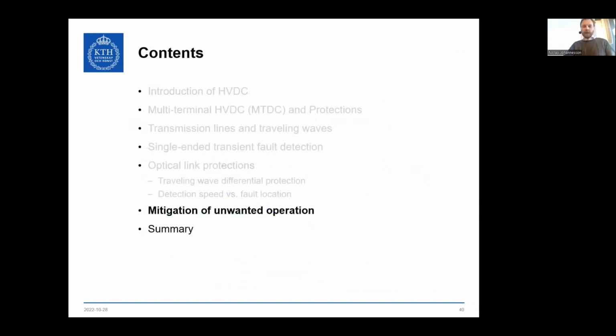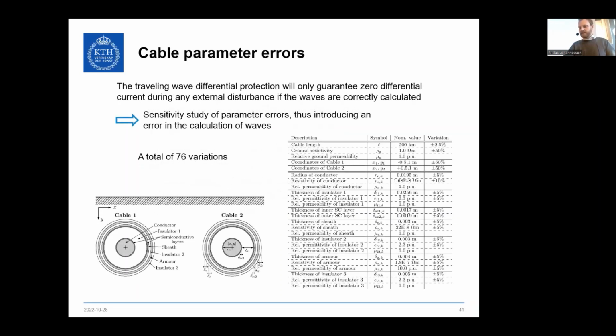Now the final parts, which I'll go through quickly. Because we rely heavily on the internal representation of the line, you need to know exactly the characteristic admittance and propagation function. The question is what happens if you don't know them perfectly, which results in a false differential current during external faults. So I tried putting small differences in each parameter to see which ones were actually critical.